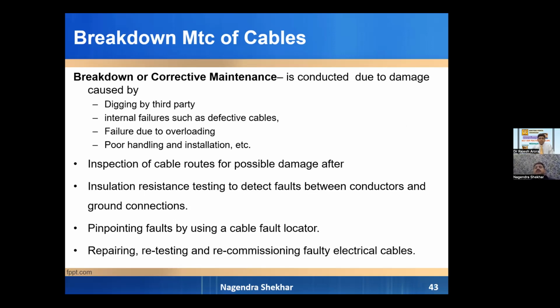Breakdown or corrective maintenance: again, we have to do nothing but make joints or replace the defective portion of cables. Recently, one of my engineers replaced an entire cable. The reason was the cable became faulty and the entire cable was running adjoining a storm water drain under trees. The trees had grown there over time as part of our DDA landscape, and the entire cable is passing through those routes. So as per the court's directive, neither can we cut those trees nor damage them. So we had to replace that entire piece of cable.